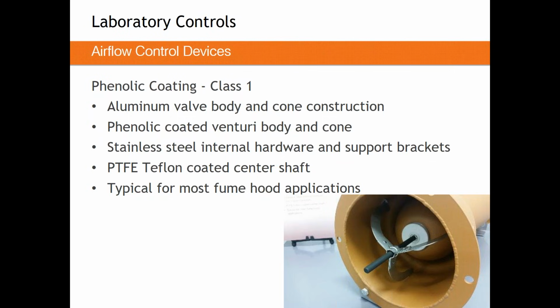Where you need chemical resistance with a Venturi valve, instead of going with a stainless steel valve, which would be costly to buy the sheet metal, costly to spin, expensive to hang, expensive and heavy to mount, you should go with a phenolic coating. It's much, much more cost effective, to the point where most manufacturers don't spin a stainless steel valve. It's really just not cost effective.